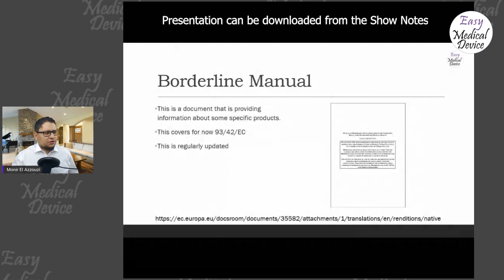Yeah, I have one important thing, maybe Rule 22. I didn't look at this one, but Rule 22. I put Rule 22 in one of the examples. Rule 22. No, Rule 21. Maybe you are thinking. Let me check. It's Rule 21 normally. Rule 21. There are substance-based devices. Rule 21 is changing completely the game for medical device manufacturers, but we'll see that with an example, because products that were class 1 are now class 3. So it's a bit strange, but it's changing the game for a lot of manufacturers.